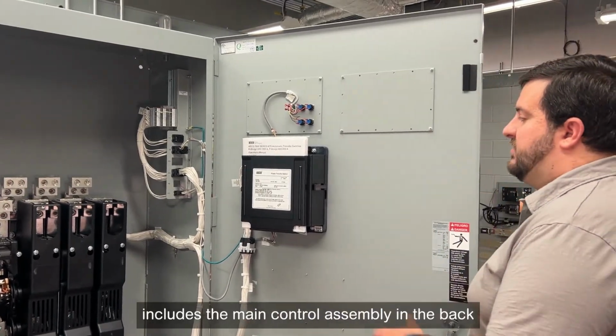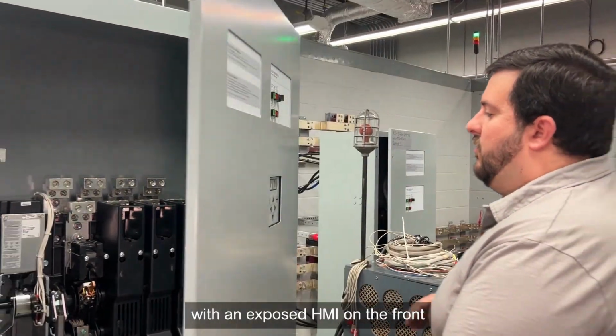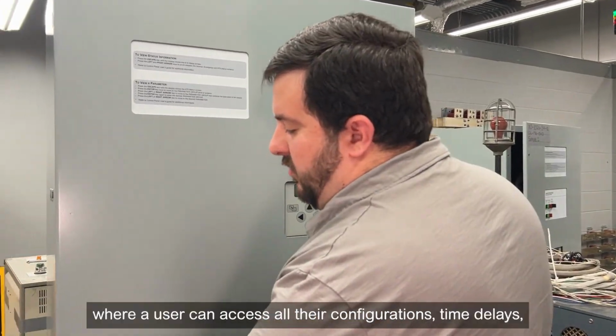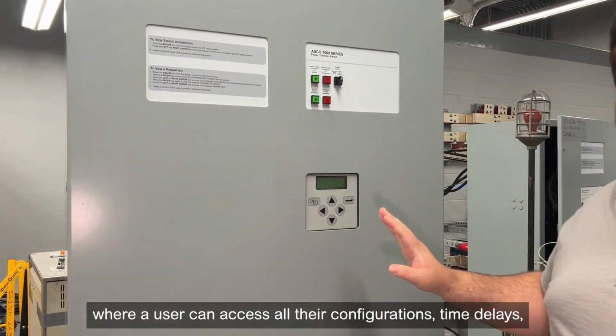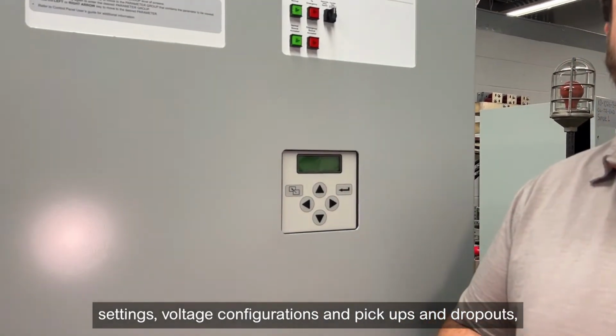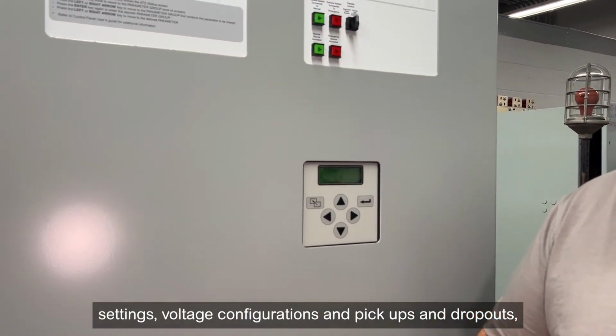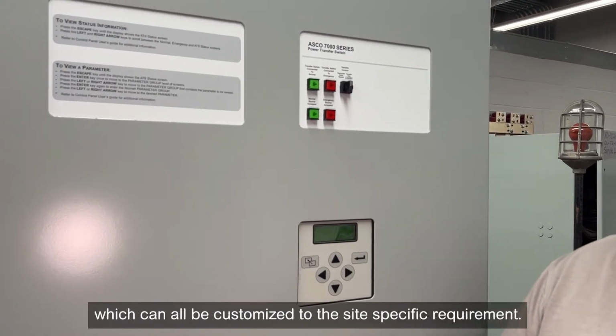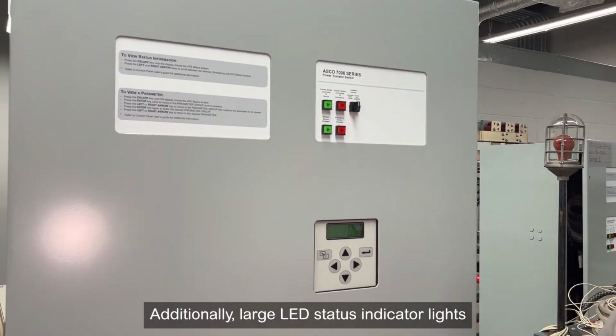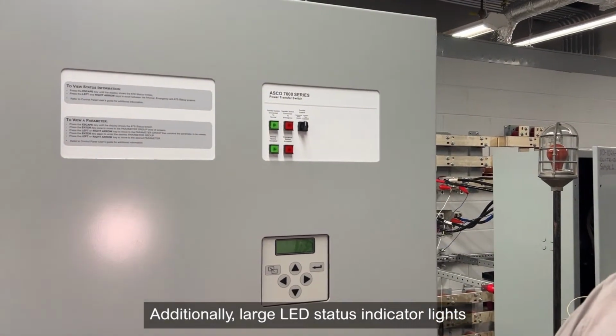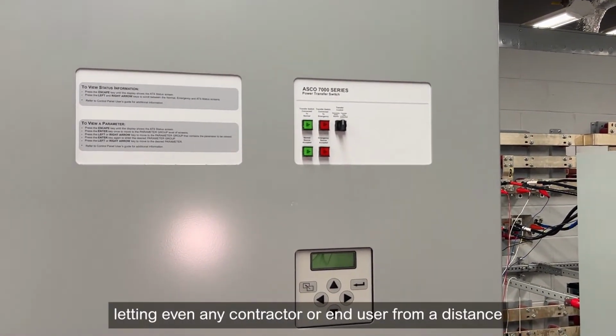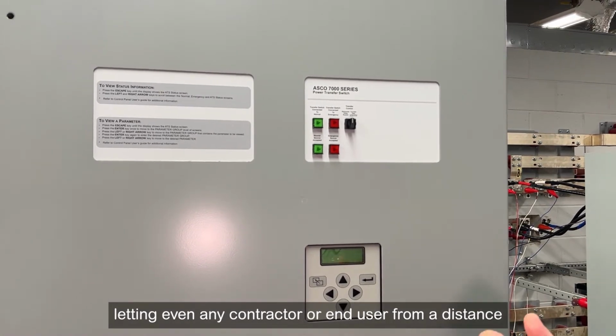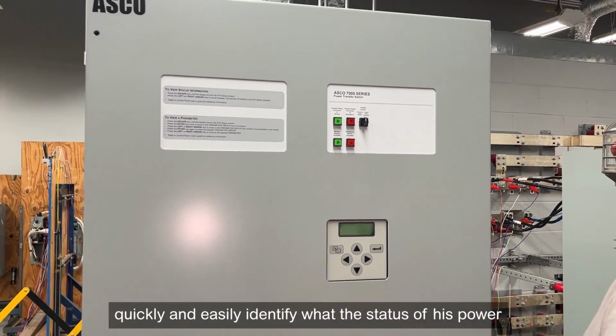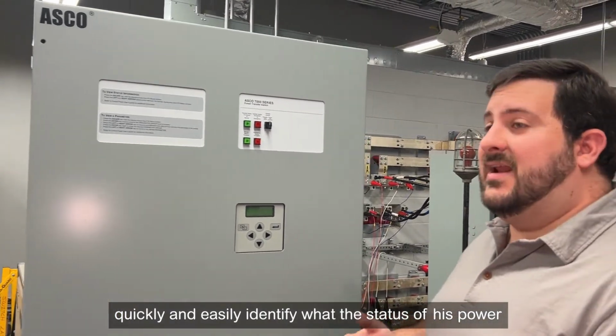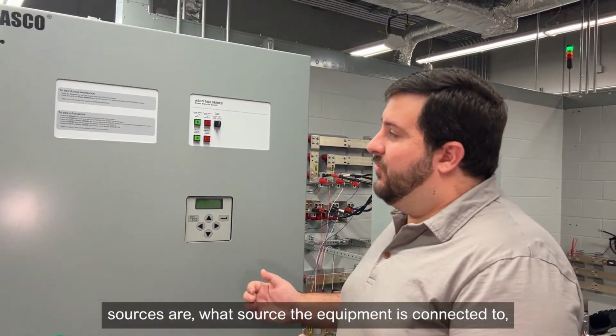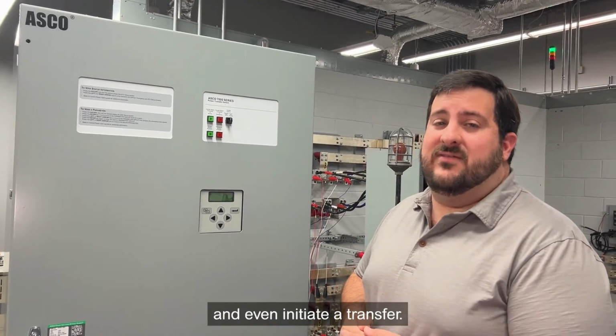The transfer switch includes the main control assembly in the back, with an exposed HMI in the front, where a user can access all their configurations, time delays, settings, voltage configurations, and pickups and dropouts, which can all be customized to the site's specific requirements. Additionally, large LED status indicator lights provide the status of the equipment, letting even any contractor or end user from a distance quickly and easily identify what the status of the power sources are, what source the equipment is connected to, and even initiate a transfer.